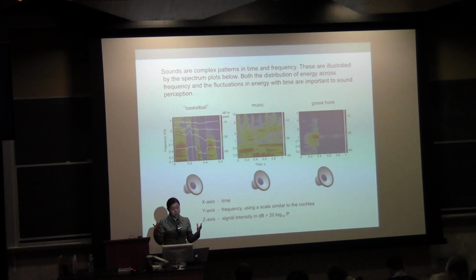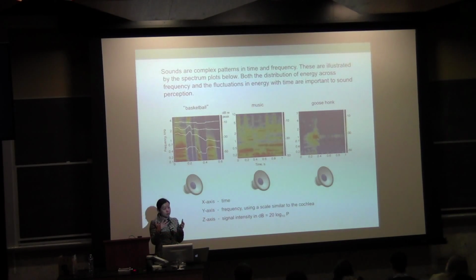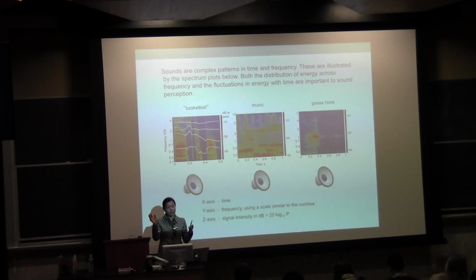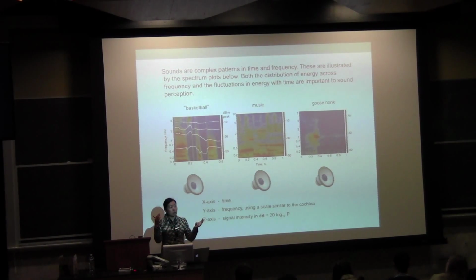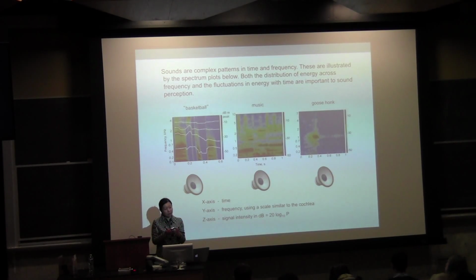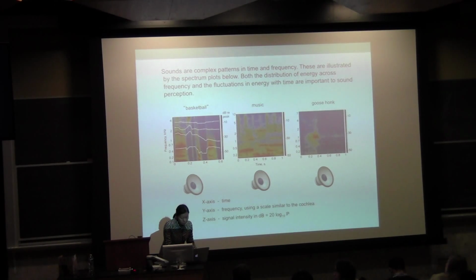And then in general, for speech perception, remember a cochlear implant is designed to restore basic hearing function, speech communication. For speech, the most important frequency range is about 100 hertz to 5,000 hertz. There's some higher frequency energy, but if you low pass filter out that high frequency energy, it's fine. Your speech perception will still be fine. So even though a human ear has a hearing range from 20 hertz to 20K, for designing a cochlear implant, you just need to think about coding the information between 100 hertz and 5K, which should be good enough for speech perception.